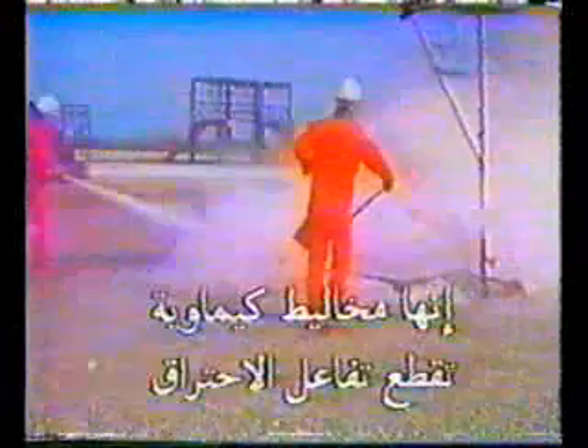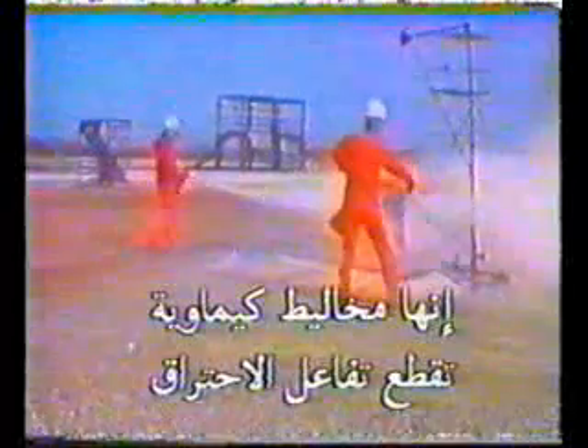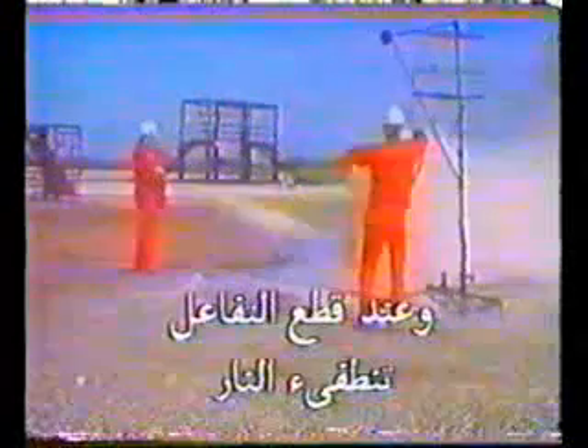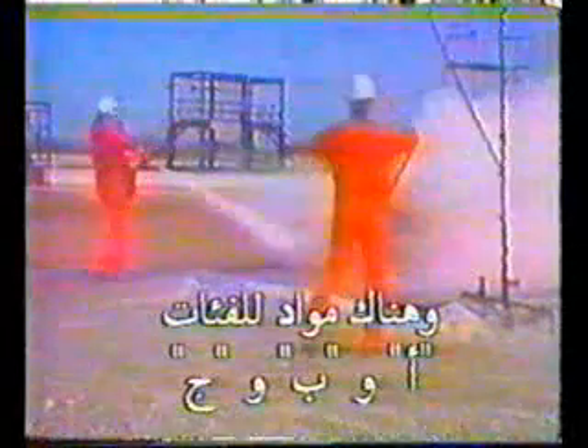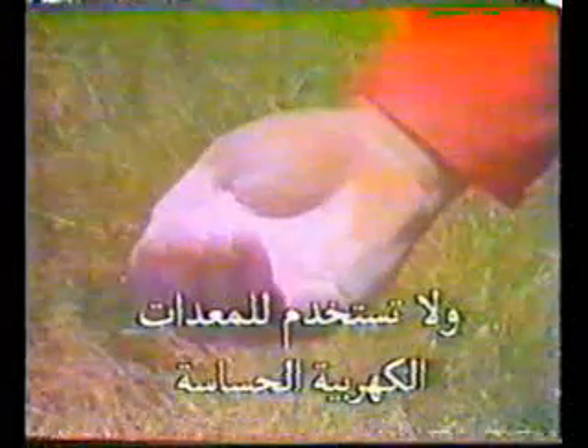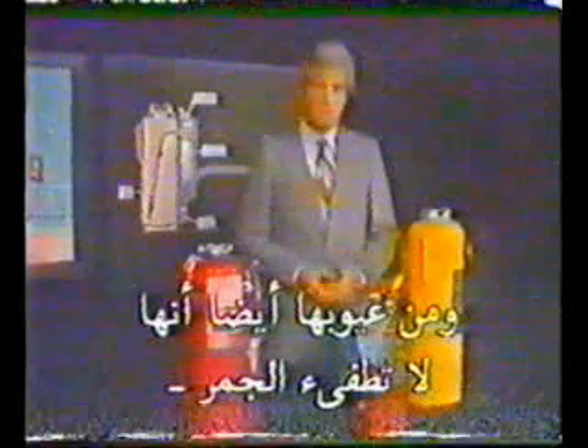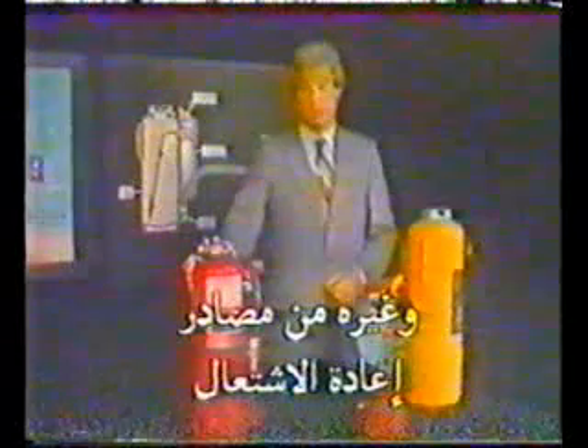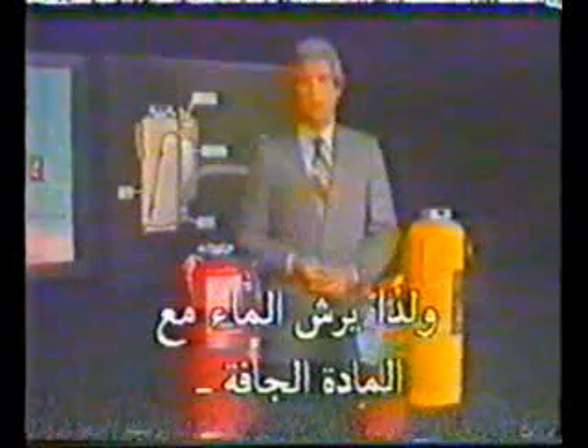Dry chemicals are a fourth type of extinguishing agent. These are chemical mixtures that interrupt the chain reaction of combustion. When the reaction is halted, the fire goes out. Dry chemicals are available that can extinguish Class A, B, and C fires. These chemicals, however, are not normally used on sensitive electrical equipment because they leave a residue which is difficult and expensive to remove. Another limitation is that dry chemicals don't extinguish smoldering embers and other potential sources of reignition. So water is usually applied before or during the application of chemical to avoid reignition of the fire.